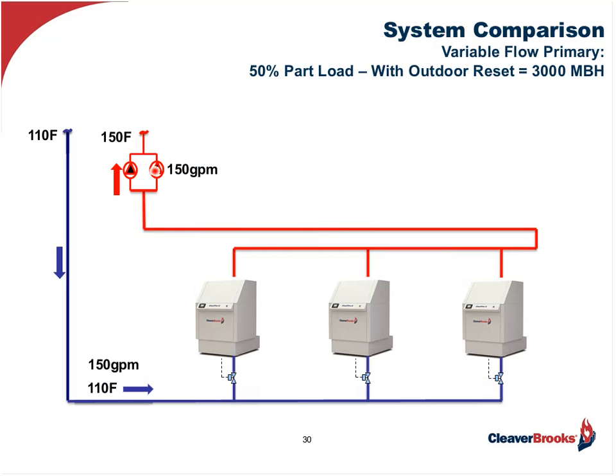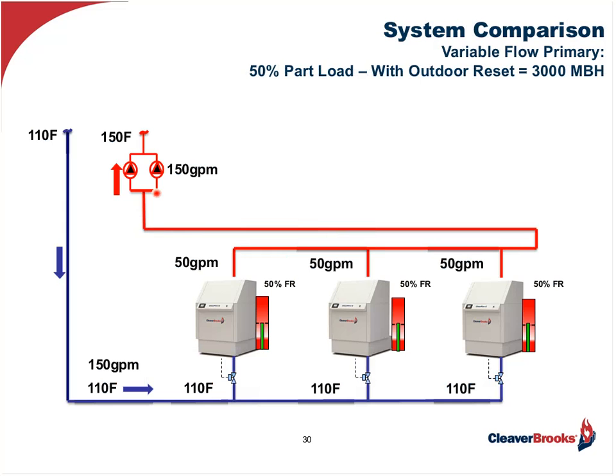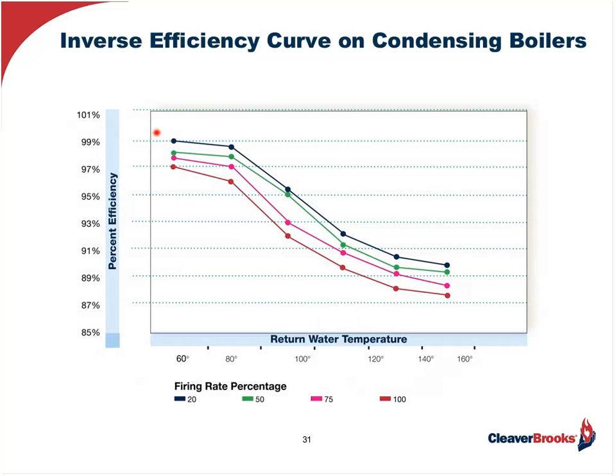Now, comparing that again, the system doesn't change. All three boilers will operate. This is critical. Here we're operating three boilers. So what happens? The boilers are going to see 110 degrees, not 120. But because all three of them are operating, they're now operating at roughly a 50% firing rate in lieu of that 75. Remember the efficiency curve I showed earlier? The lower the firing rate, the higher the efficiency with condensing boilers. So without even taking into account that they're getting colder water, we're going from about 75 to 50, we're picking up 0.5% to 1% efficiency on the boilers alone. Again, it's not a lot, but when you're trying to design a high-performance building, every percent helps.